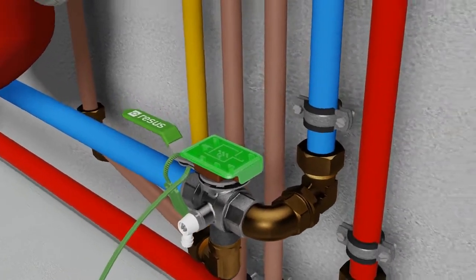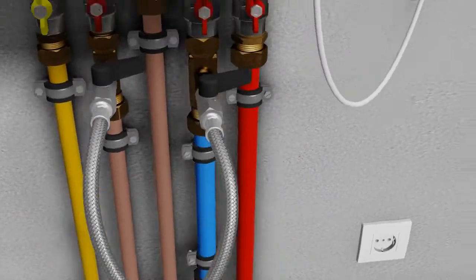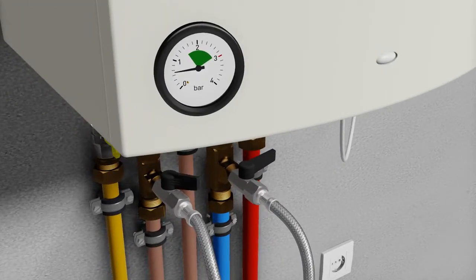In this way we set the cold fill pressure back to the correct value, making sure that nowhere in the system air or oxygen could get in.